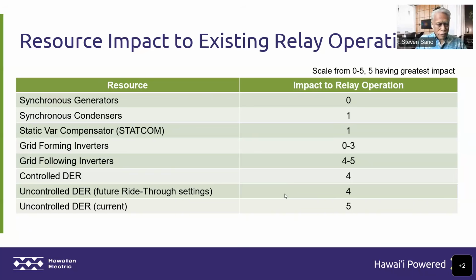Grid forming inverters versus grid following inverters. This is sort of a very interesting area that is evolving on our system. Current indications are that grid forming inverters will address, to a certain extent, the issues that we're seeing with the weak grid issues. So grid forming inverters, because they offer more flexibility, more capability in terms of fault current behavior, in terms of voltage support and frequency support. Grid forming inverters, we think, will range from 0 to 3 on the impact to our protection systems.